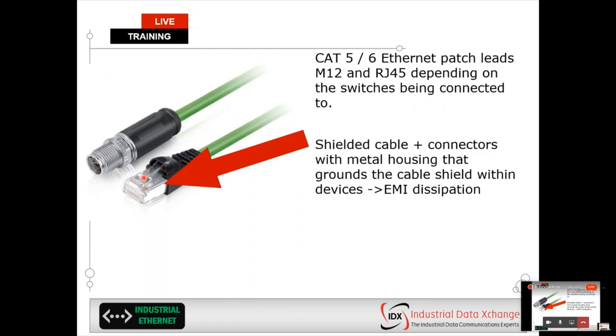But that shielding is completely useless unless it's grounded at multiple points in the network. So the industrial Ethernet cable you're utilizing should have industrial Ethernet connectors. This metal housing on the outside of the RJ45 and the M12 actually grounds the shielding of the cable to the device you plug it into. That device in turn grounds the shielding directly to the DIN rail. So ensuring there's continuity between your DIN rail and a functional grounding point is very important.